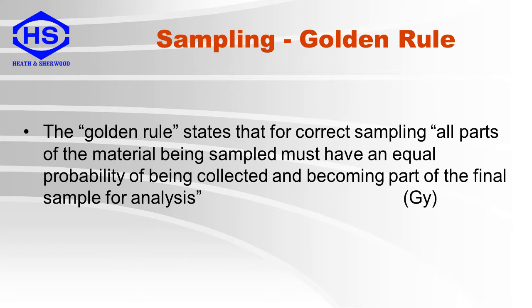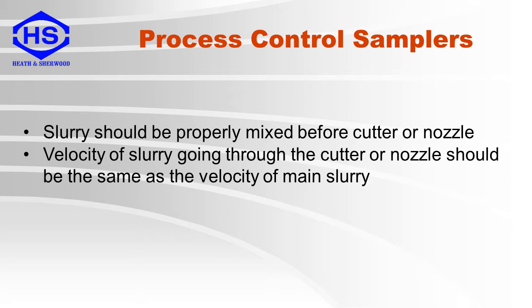It should be stressed that process control samplers do not respect the golden rule for sampling and therefore are not probabilistic. The slurry should be properly mixed or homogeneous before getting to the cutter or nozzle. The velocity of the slurry going through the cutter or nozzle should be the same as the velocity of the main slurry. However, there is no guarantee that this is really the case because of changes in the process and piping.